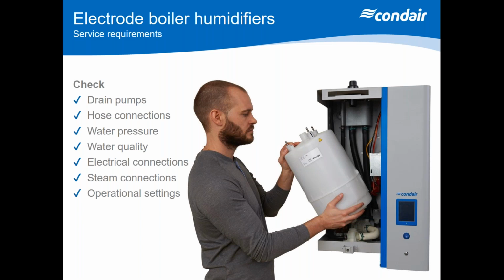Water quality, as I say, we're all looking at hard water, but you may find in places like Scotland the water is exceptionally soft. So you might have to fit a different type of cylinder, or it may be too low and you can't get it to work at all. You can put salts in and Alka-Seltzer in, but it will only work for a short period of time.